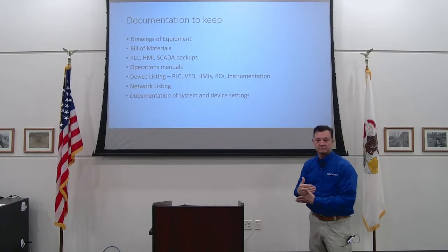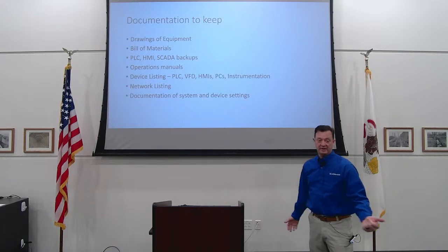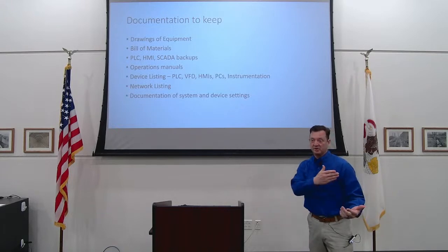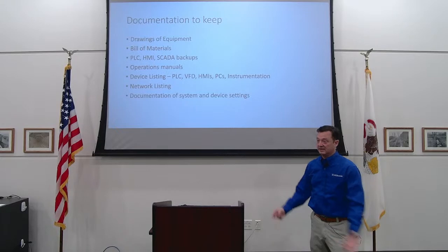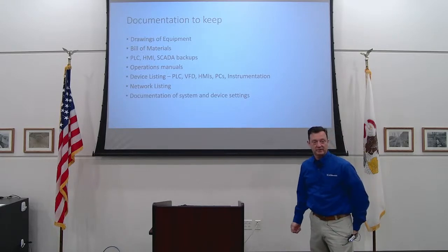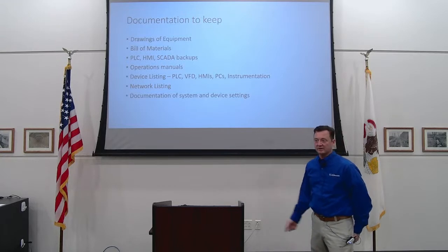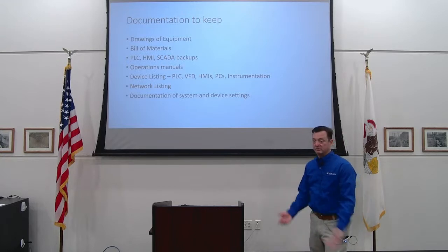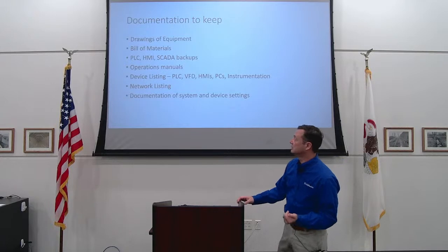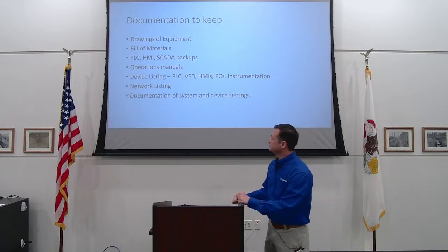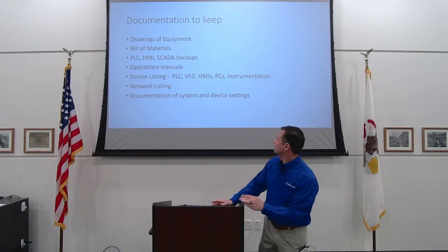I'll say, personally, I've had a customer site - a water treatment plant - where the entire Slaker building went down because they didn't have segregated networks. Somebody plugged a printer in and it got the same IP address as the Slaker system, and they lost the lime system for the water plant. So, documentation of device and system settings is important.